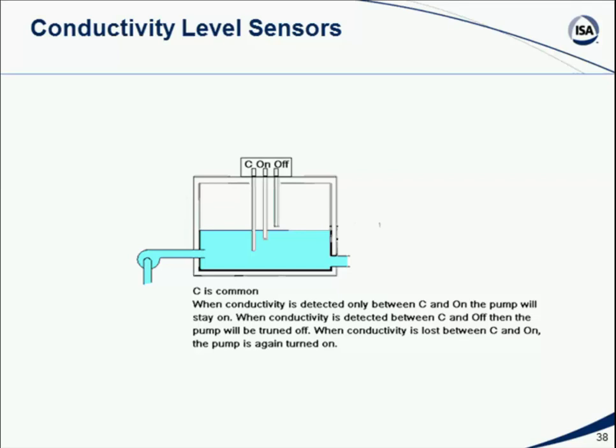So once the level reaches the on probe, anywhere from there upwards, we can see that there is conductance between the C probe and the on probe. We can't tell you what the exact level is. All we can tell you is that the level has at least reached on. Once it reaches the off probe, we can measure that and tell you that the fluid level has at least reached the off level. So, of course, it's above the on level, but it's at least reached the off level. How far above that, we don't know. If you really need to know, then you either need to use some type of continuous level measurement or you need to stick a few more probes in. But in many cases, in certain types of tanks and applications, we don't really care what the absolute level in the tank is.